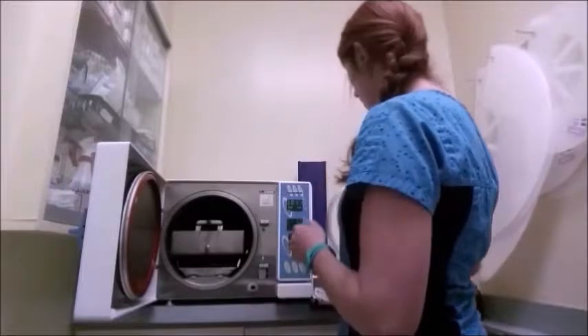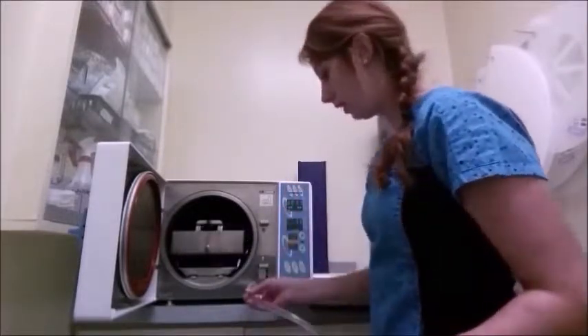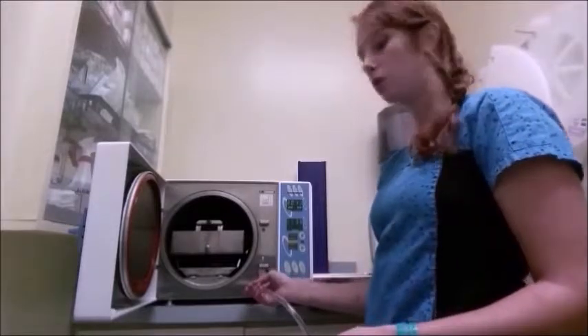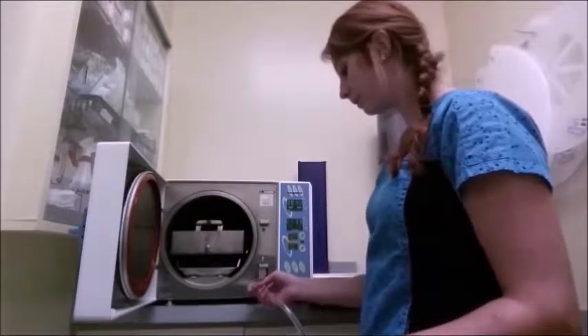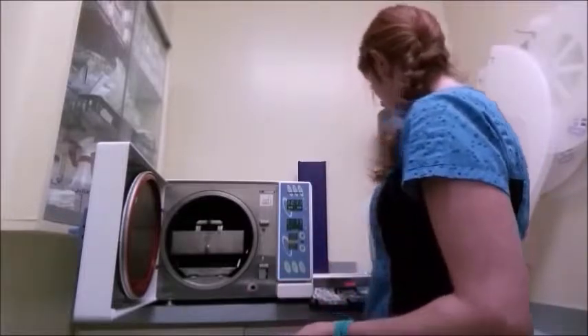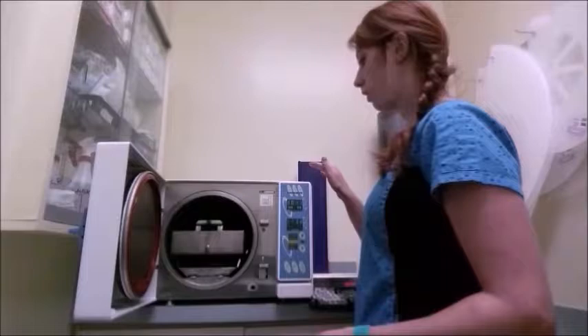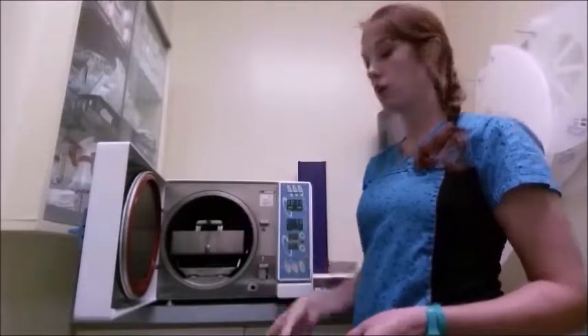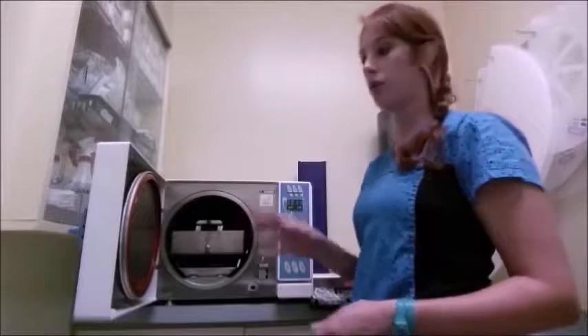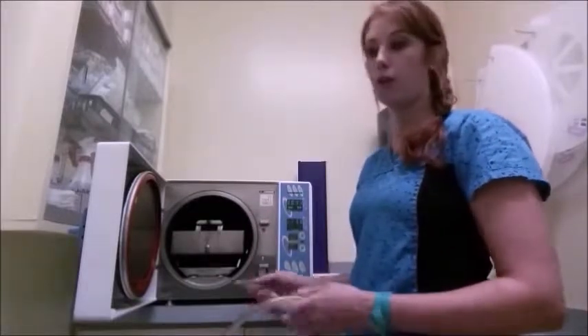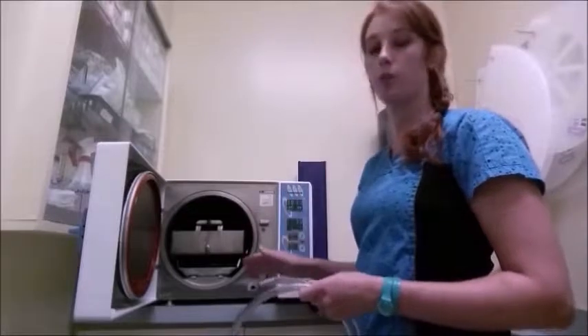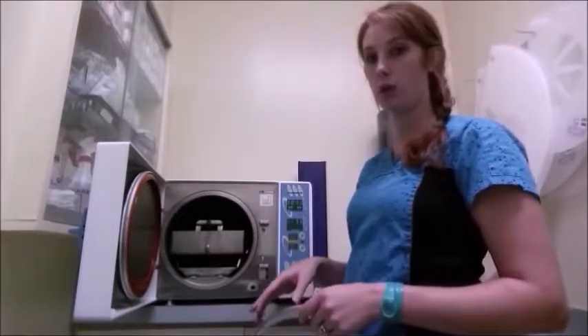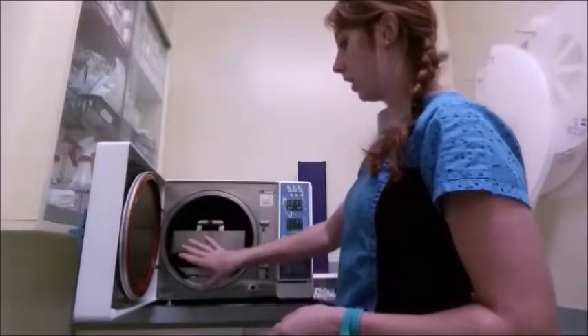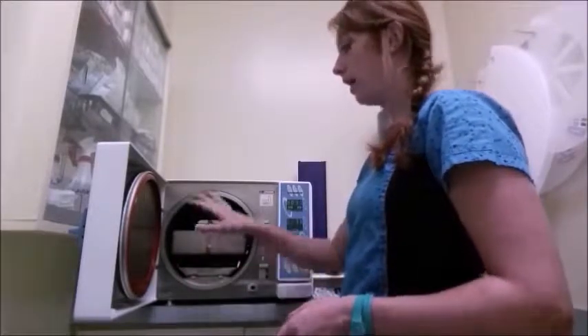Every 25 cycles, the unit also needs a full cleaning. To do the full cleaning, we have a piece of tubing that allows us to connect into our water reservoir to do a quick drain, which removes all the water from the unit. We then place a cleaning solution into our reservoir along with a specific amount of distilled water. We run a cleaning cycle on the autoclave, then drain out the water again, fill it back up with some more water, and drain again so that we can remove all of the suds from our autoclave. While we're doing that, we can also take our tray and support stand out and give everything a good scrub and clean.